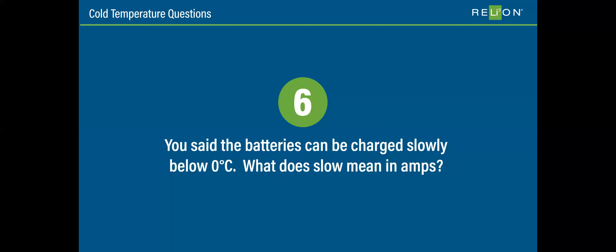When you get into lines 3 and 4, I'm going to switch to Celsius on you: from freezing to -10°C is one segment, and then from -10°C down to -20°C is another. In battery terms, you want to charge at 0.1C for the first and 0.05C for the second. Those coefficients, 0.1 and 0.05, really translate to 10% of C or 5% of C. What is C? C is the amp hour rating of your pack, or your one battery if that's what you have.